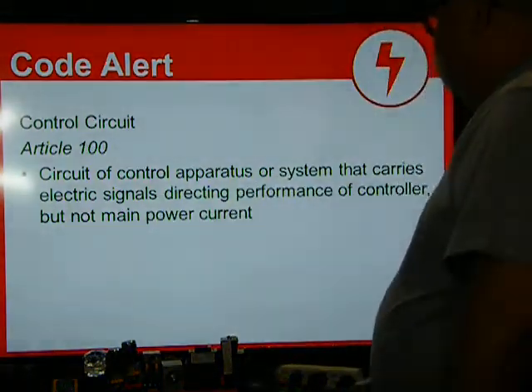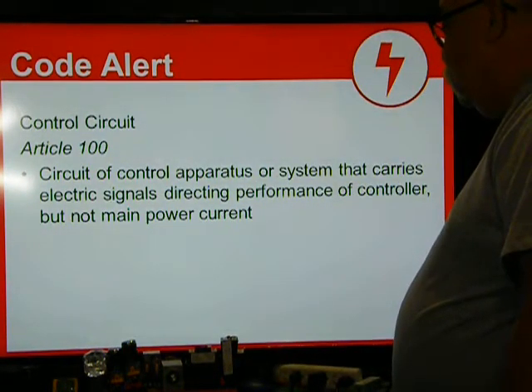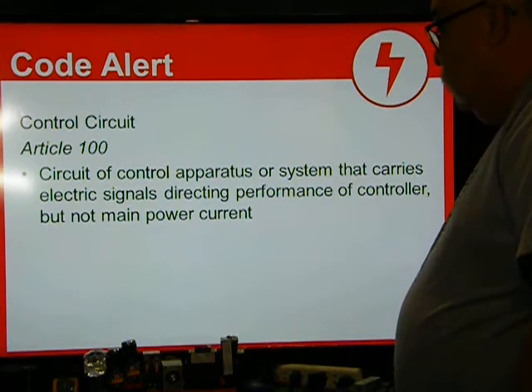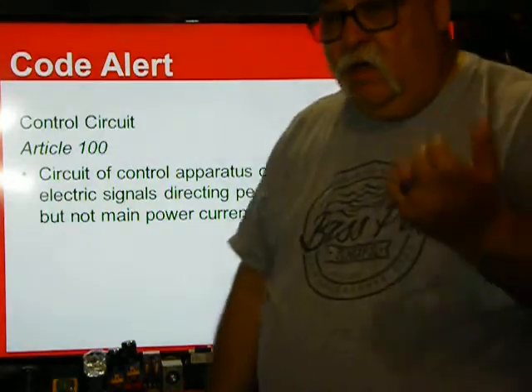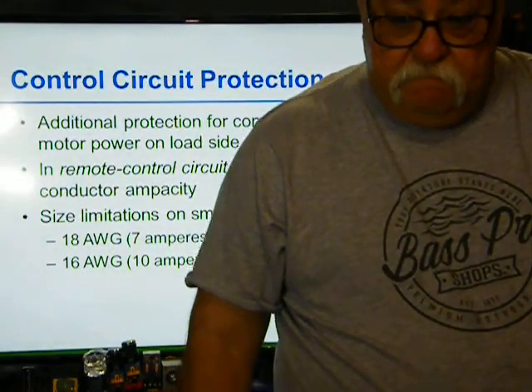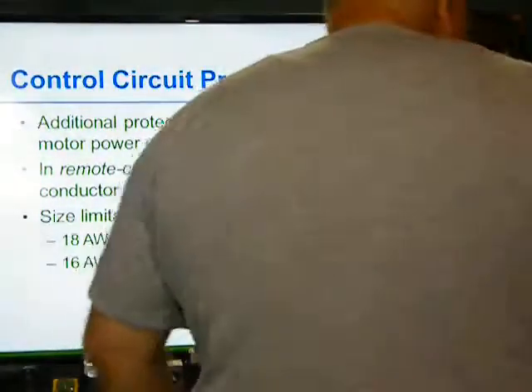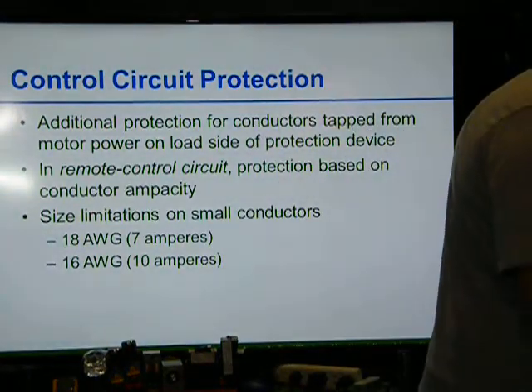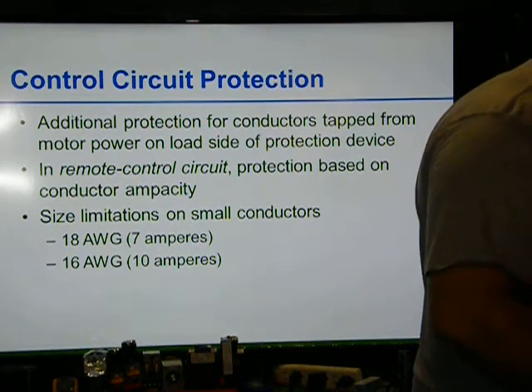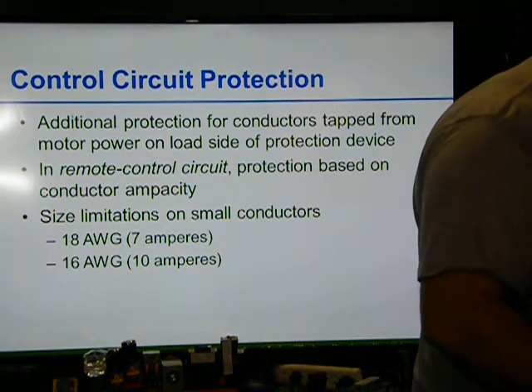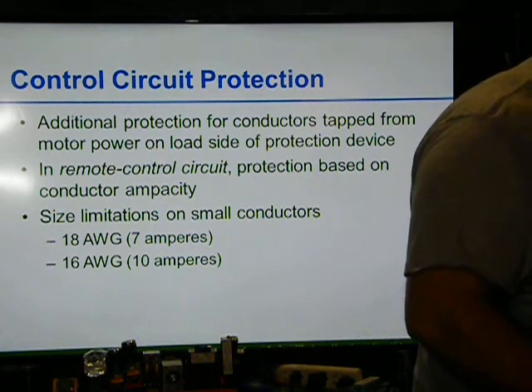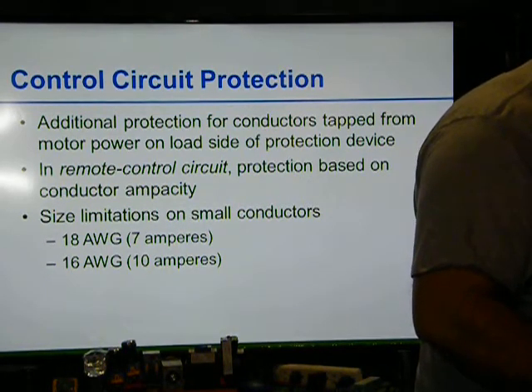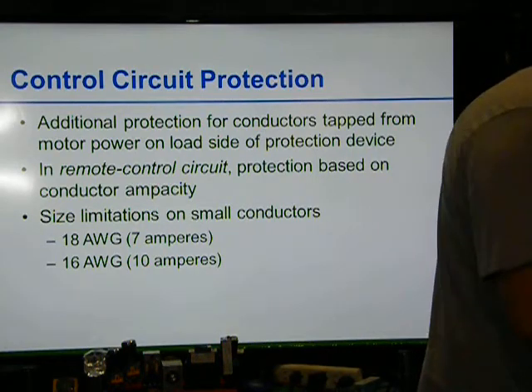Control circuit, Article 100: a circuit of a control apparatus or system that carries the electrical signals directing the performance of a controller, but not the main power current. So that's what I was talking about. It's only carrying the current of the controller. Control circuit protection says additional protection. Well, let me go over this before I get to that. The motor circuit carries the high current used to run the motor. The motor control circuit only carries a lower signal current used to direct the function of the controller. In most cases, the controller is rated at 120 volts or less. A control transformer is used to reduce the voltage of a high voltage supply.